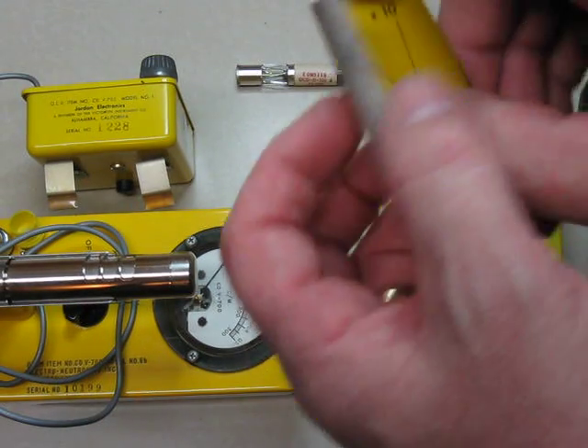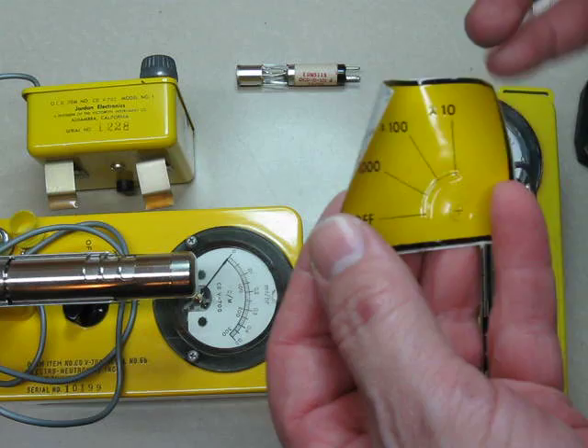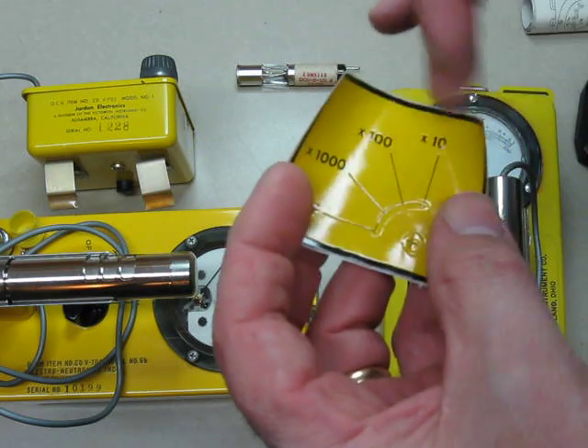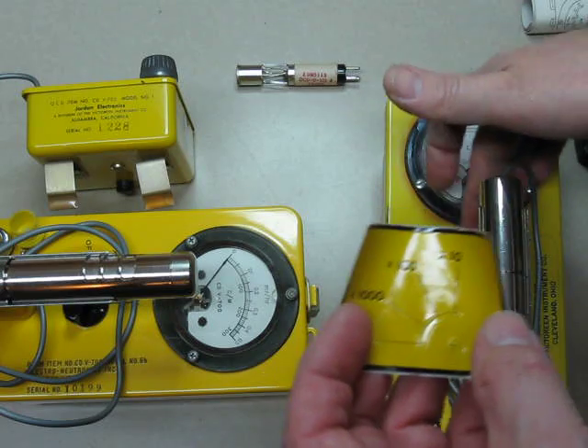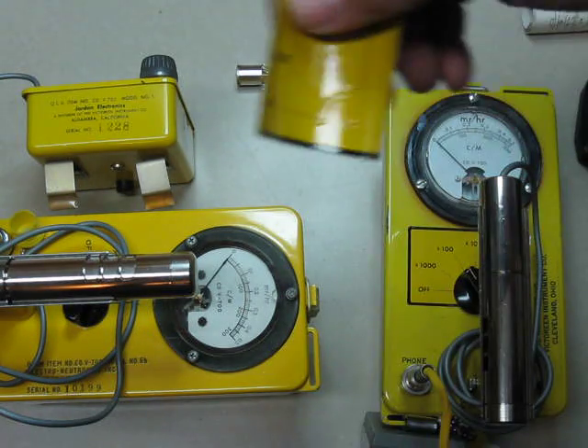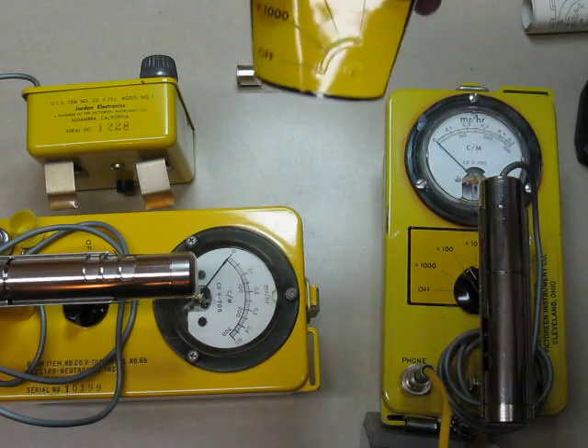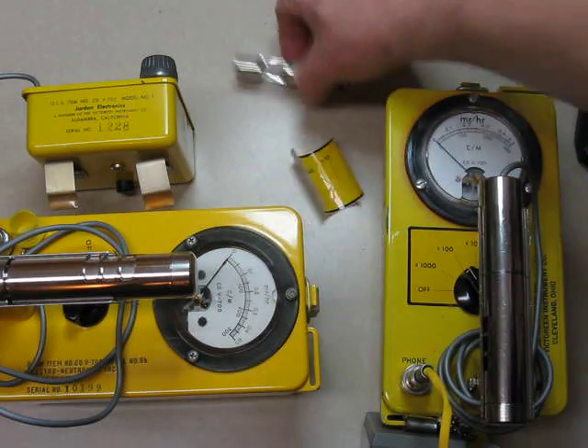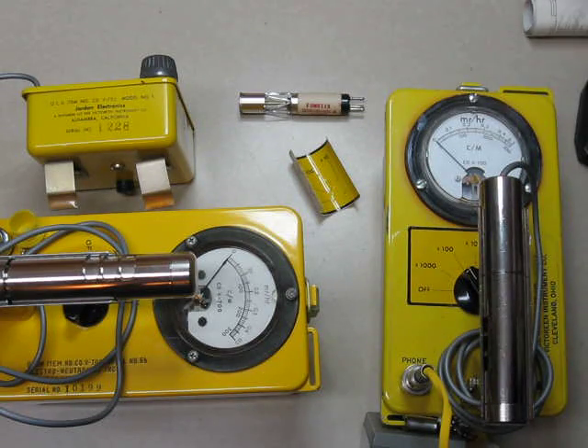These were issued as kits. It came with a tube and a sticker. It would change the range - it would multiply it by a factor of 10. So on the 700, when you put the sticker on it, the one range would be 10, the 10 would be 100, the 100 would be 1,000. All you'd have to do is put this tube in and put that sticker on, and it would multiply the detection range of the 700 by 10.